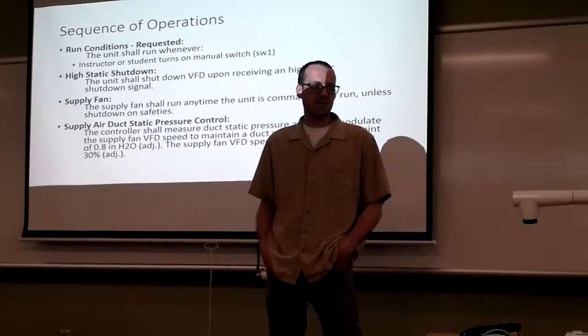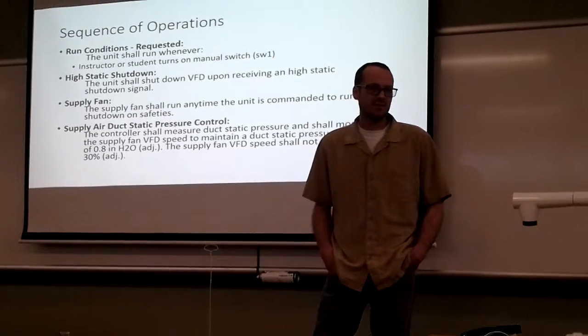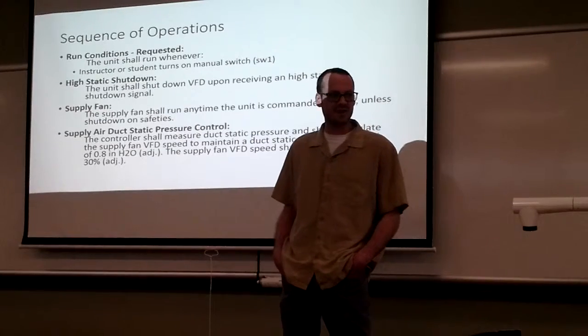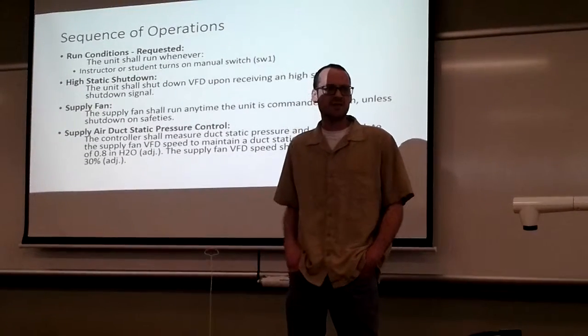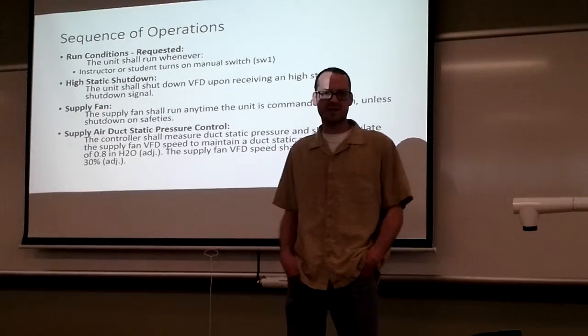Some of the safeties are supply air duct static pressure control. The controller measures the duct static pressure and will modulate the supply fan VFD speed to maintain the duct static pressure set point of 0.8 inches water column. It's adjustable depending on the size of the duct.